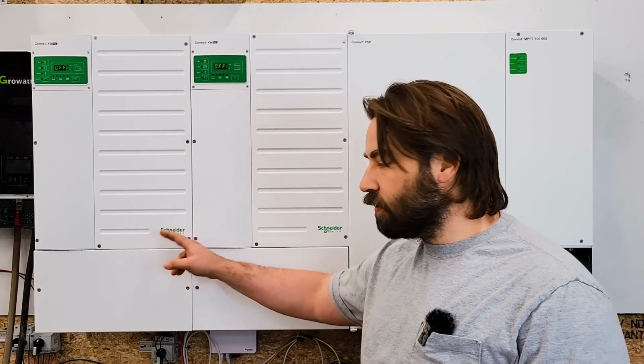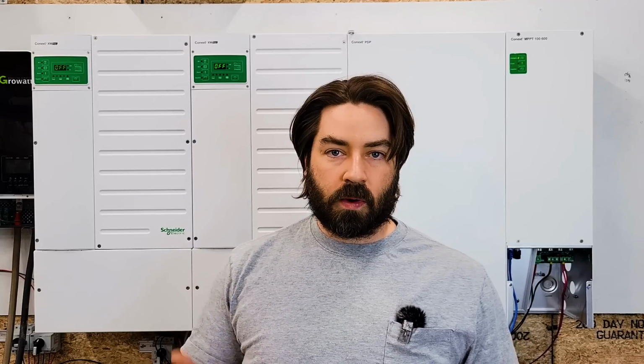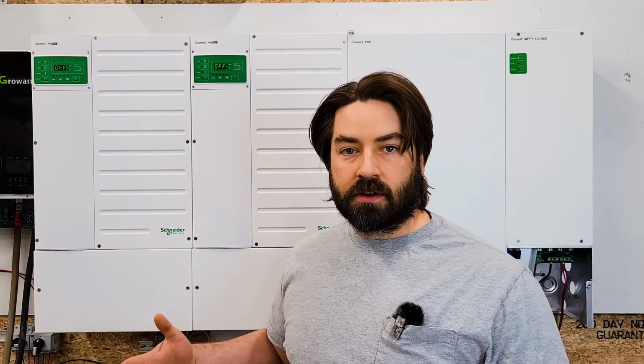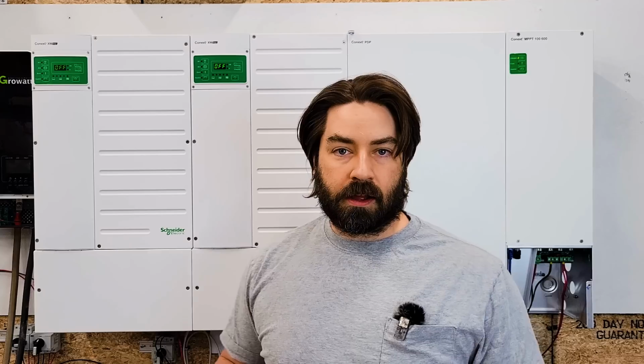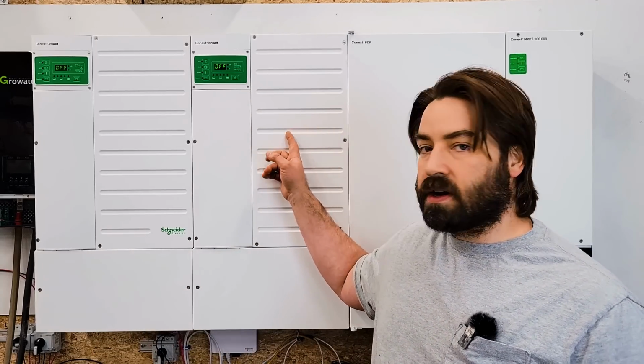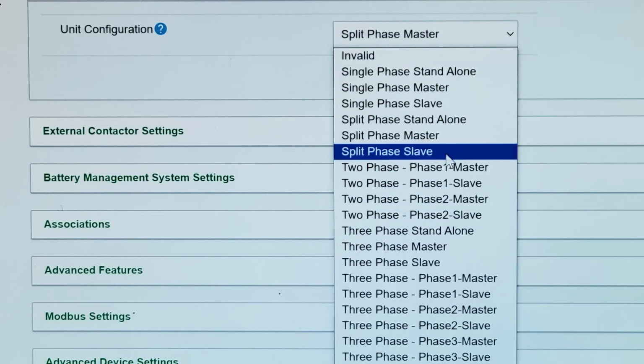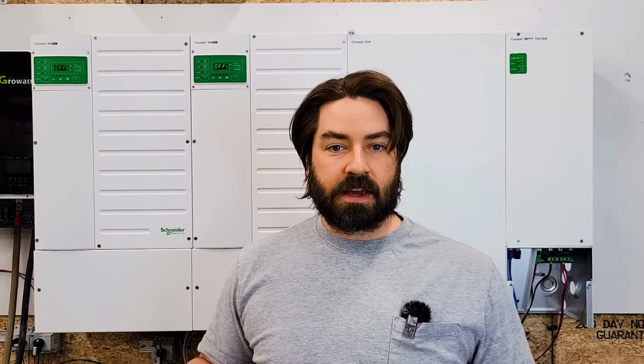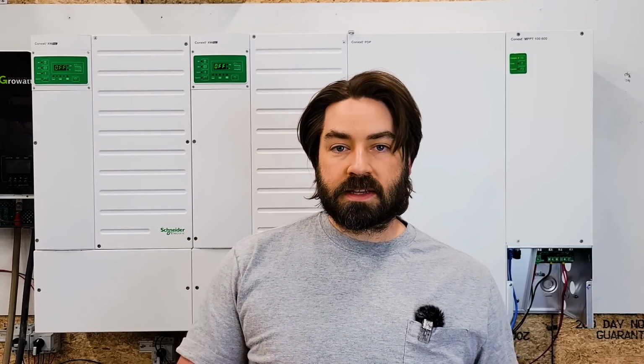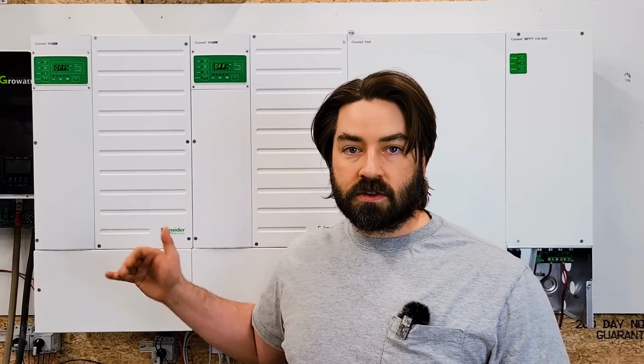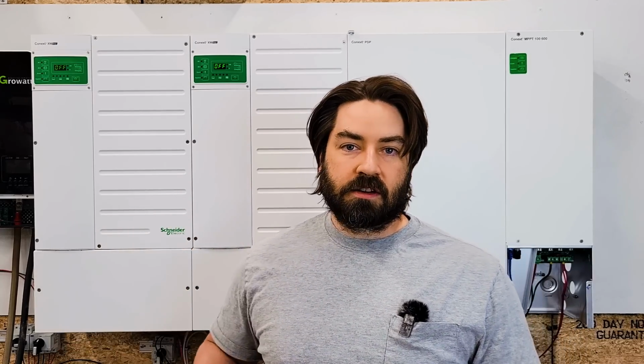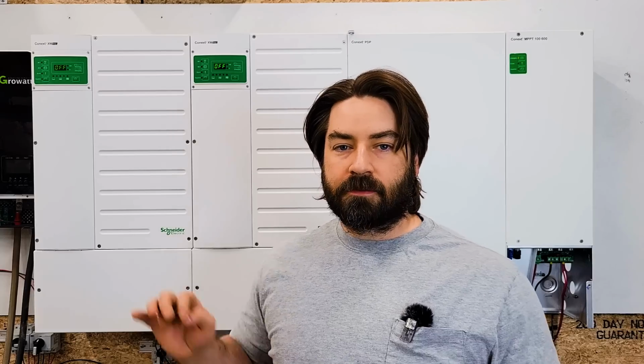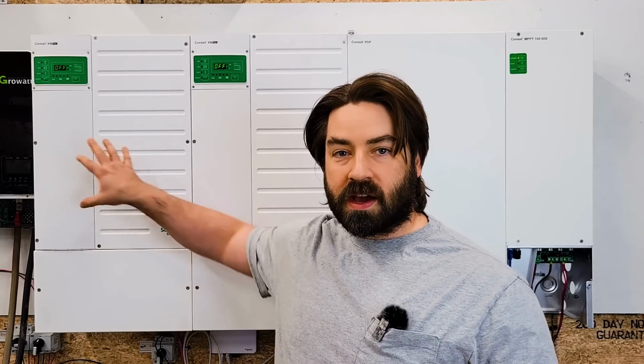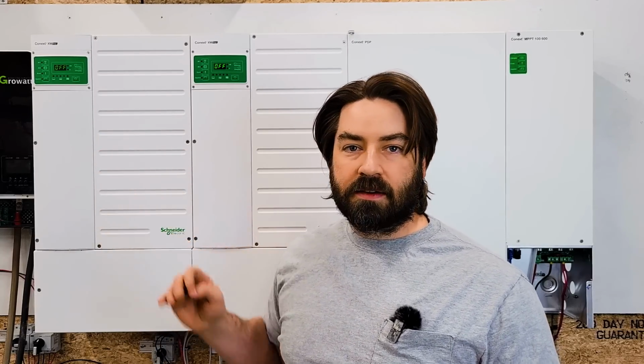Once those were updated, then I could finally reconnect all the communication wires, the Xanbus and the sync wires between the two, and now I could set them up to work in parallel. One needs to be set up as the master, which is right here, and the second one needs to be set up as the slave unit. Now you need to make sure that they're labeled as split phase master, split phase slave, because there's also an option for single phase and three phase. These are running in split phase orientation, which is North America standard 120/240. Now the last thing to set for getting this inverter to turn on, because this whole time this inverter's been in fault mode, is you have to set a device number.